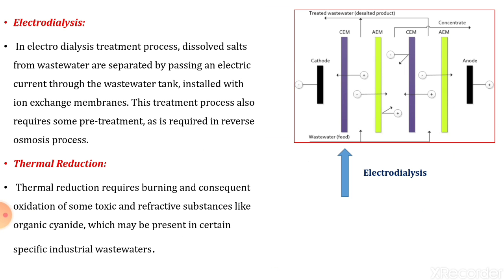In the electro dialysis treatment process, dissolved salts from wastewater are separated by passing an electric current through the wastewater tank installed with ion exchange membranes. This treatment also requires some pretreatment as required in the reverse osmosis process. The wastewater or influent is fed from the bottom, coming into contact with the anode and cathode electrodes, which are charged. Undesirable pollutants, cations and anions, get attracted towards the electrodes causing their removal and separation. The treated wastewater is taken out from the top, and the concentrates accumulated in chambers, called brine, are also removed.